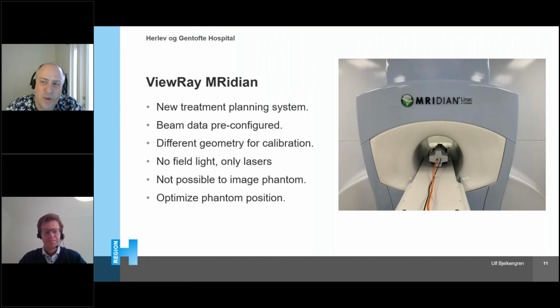Yeah. Okay. So we have QA on the lasers daily compared to an imageable phantom. But lasers are lasers, and especially lasers mounted on a wooden structure like a Faraday cage. You have some uncertainties in that, of course, but there is a QA routine. But then again, it is a problem for a Delta 4 Phantom, but it's not a problem for a patient because you are actually seeing the patient, but you can't see the Delta 4 Phantom.